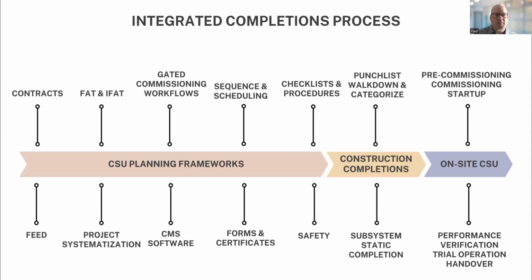And now that it's got process fluids or high voltage energization, your contracts may have a trial operating period. In some cases maybe there's a 3-day trial, a week operating period, or a 30-day trial operation period where the system needs to operate uninterrupted. If there's an unintended interruption, the trial period starts over and it must get through that to reach the end of the project, where we can hand over the facilities or deem them suitable for commercial operation and start putting systems into service.